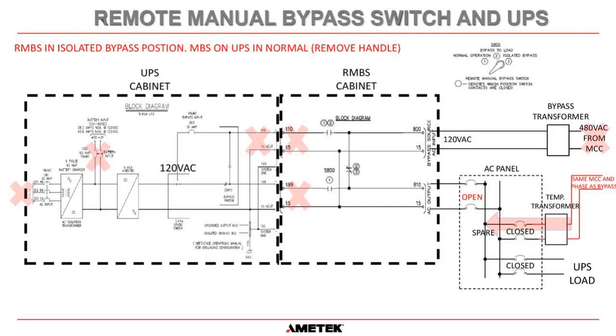And another important thing that we always recommend to do is, I don't know why my screen is showing that line missing there. It's weird, but on the bypass switch that's internal to the UPS, what we always recommend now is you put that in the normal position, and then you unscrew the handle and you take the handle off, because from now on, we're going to treat it as if that switch is not even there anymore. There's no need for you ever really to switch that switch anymore, because we've got the switch external to the system. So we always recommend that you remove the handle so misoperation cannot be performed. Okay.